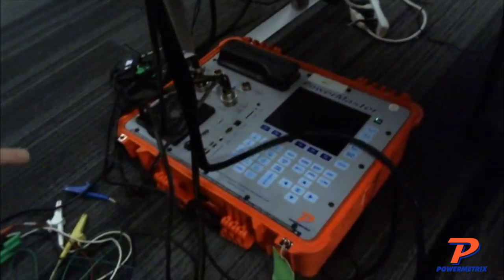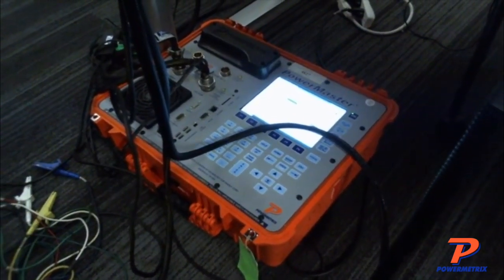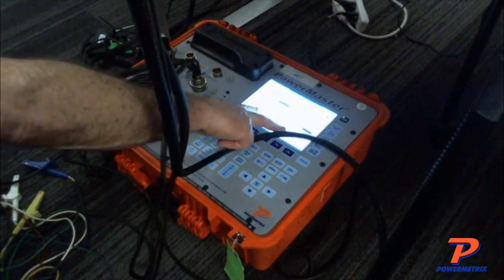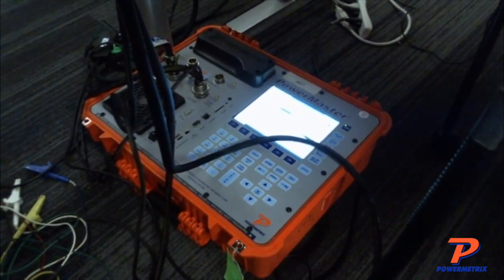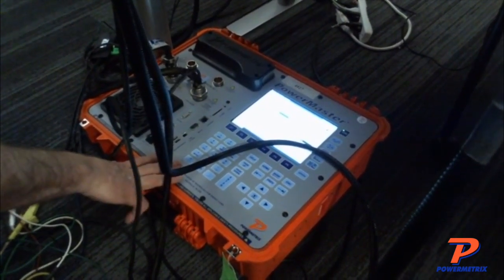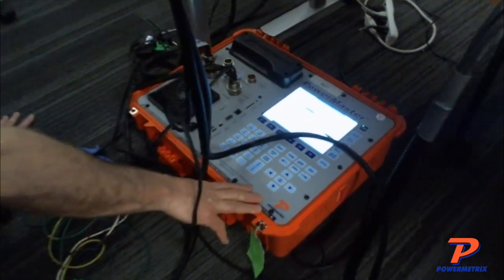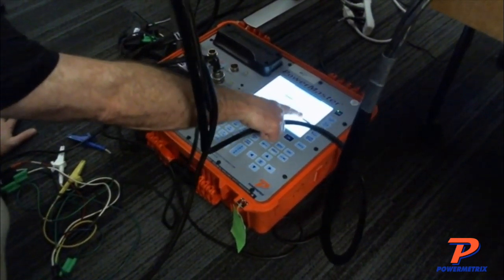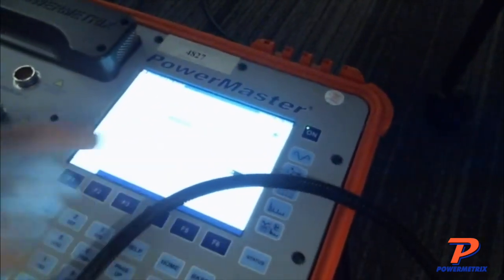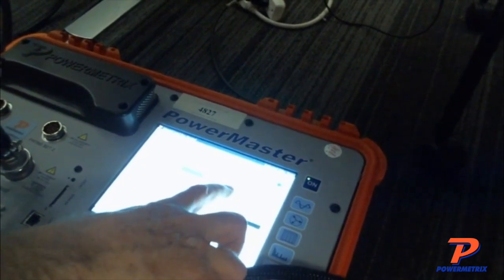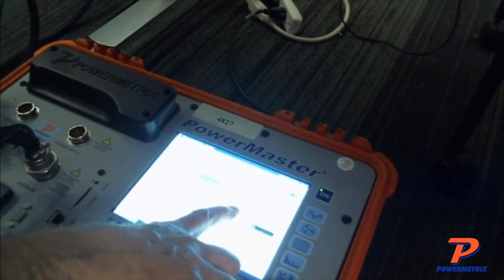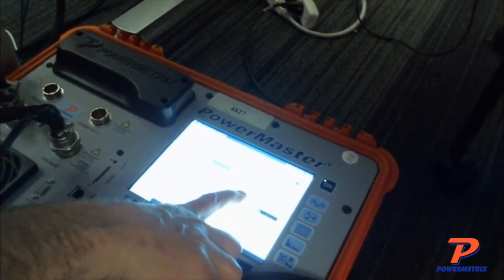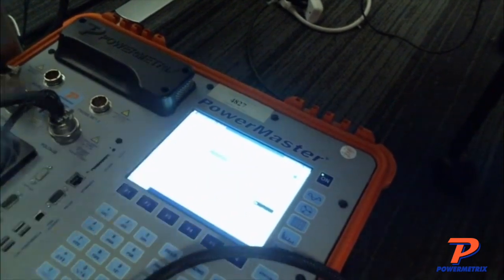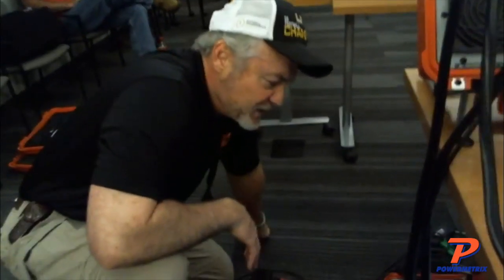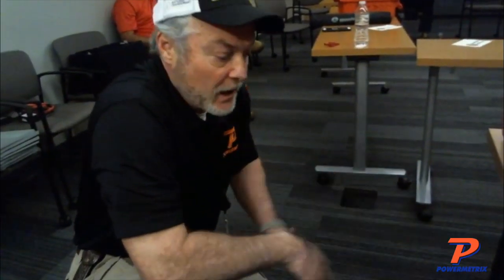Absolutely. So I'm using this—this is my source, if you will, this is the customer. So I've set up the manual load box control. And with manual load box control, this product is a 7332, so it has both voltage and a 20 amp current source, meaning I can adjust both voltage and current here. I can change the angles and I can change the amplitudes. So I made it 5 amps, which is all I have for primary current here, and that's not enough to test properly a 200 to 5 CT. That's why we're doing the load box test. I altered my angles a little bit, only because I'm a creature of habit and do that all the time when I do meter schools and demos, so I separate my voltage and current vectors. So that's how we've got it set up right now.